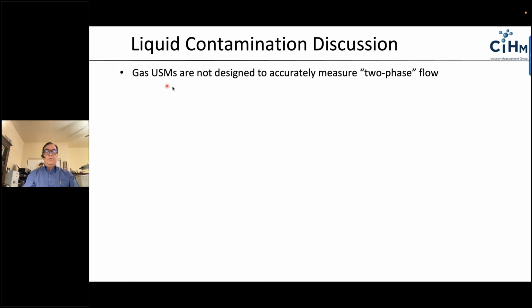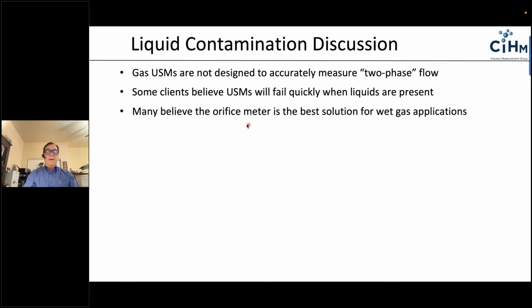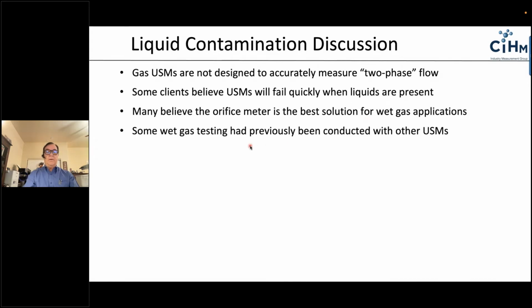To start with, we're going to talk primarily about two-phase measurement. When I say two-phase measurement, I mean there's natural gas along with some liquids. Many clients believe that using ultrasonic meters in these applications is not a good idea because the liquids will cause the meter to stop working. Many believe the orifice meter is thus the best solution for these applications because they always get a differential. The question I'll show you a little bit is about the accuracy of the orifice meter relative to the ultrasonic meter.